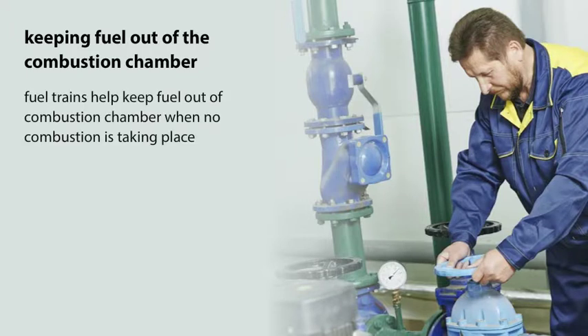Keeping fuel out of the combustion chamber. Fuel trains help keep fuel out of the combustion chamber when no combustion is taking place through a series of specially designed shutoff valves that are usually spring-loaded to close. These are called the safety shutoff and blocking valves. These valves come in different variations and configurations.